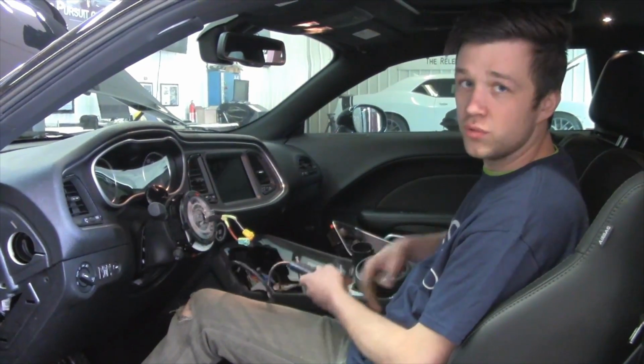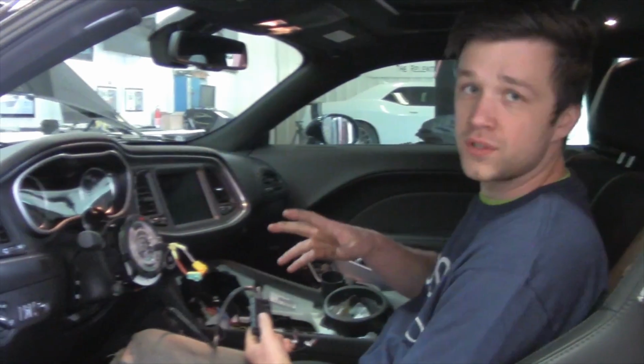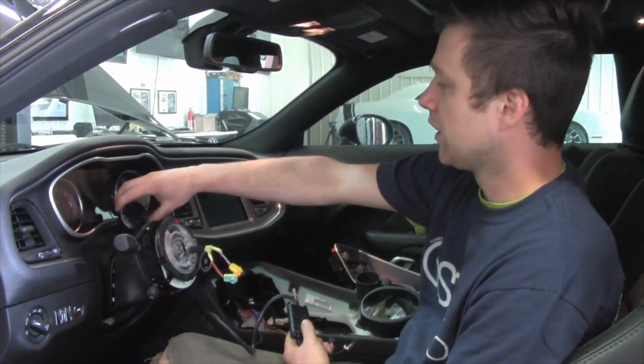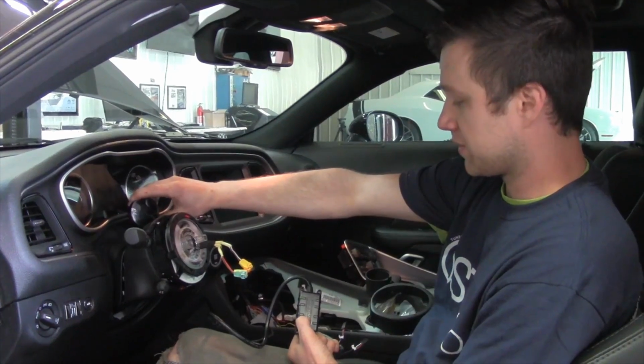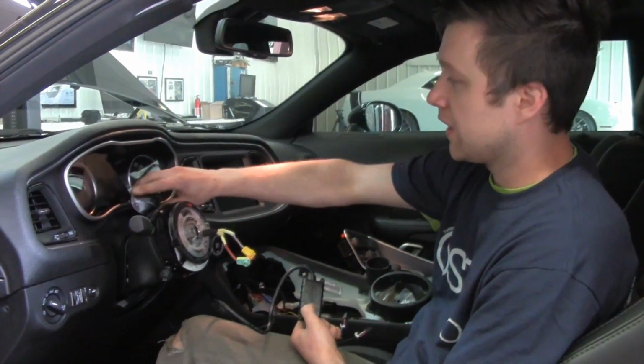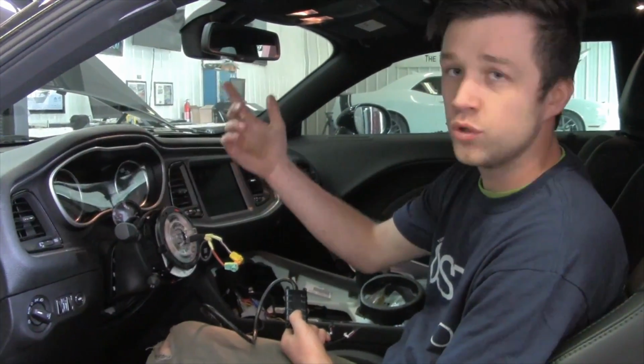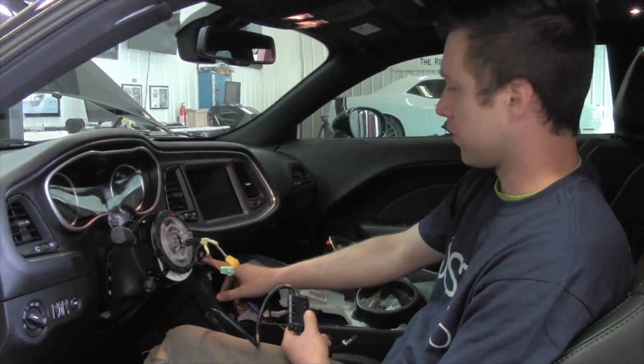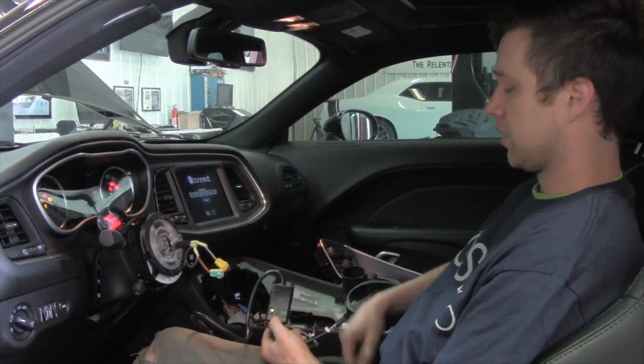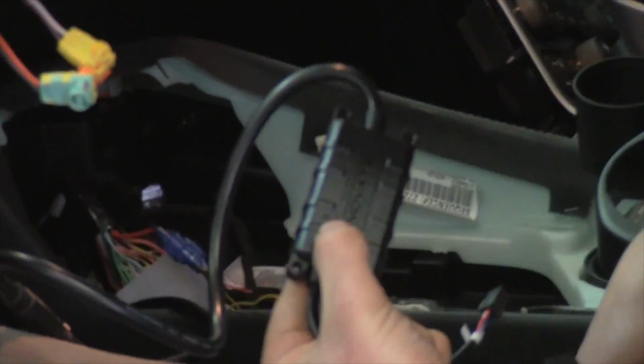Now we'll do ignition on, and they say this one's for 2 minutes, but you're just going to leave it on until the sensor warms up. That'll vary. When the sensor warms up, this will stop blinking green, it'll go solid green, and your gauge will read 22.4 or 22.1. So ignition on. The blinking green means that it's warming the sensor up. If you have a red showing now that your sensor is hooked up, that means you've wired something incorrectly, pinched wires, or maybe a bad sensor. So we'll let that sit until the sensor warms up.